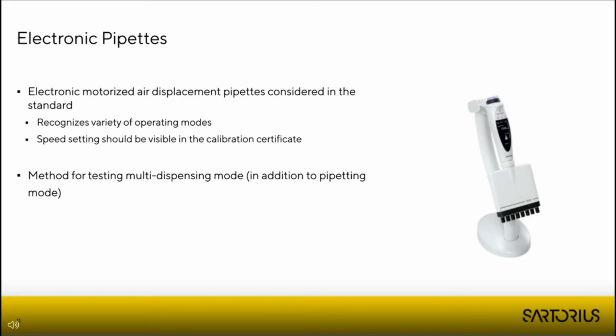And then maybe the most important thing is that now there is a method for testing the multi-dispensing mode. This is something that some manufacturers have already done before, but there was no standardized way of doing it. So it was challenging to compare the performance of an electronic pipette if you checked the manufacturer's data. But now there is a standardized way of doing it, and comparing different models should be a bit easier, which is really good for the user.